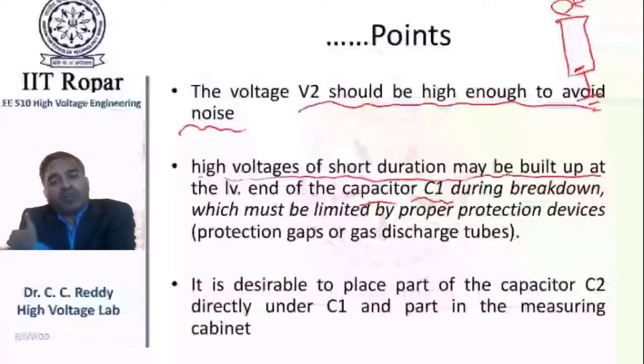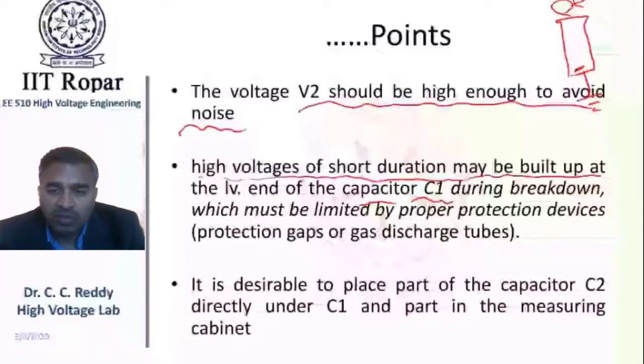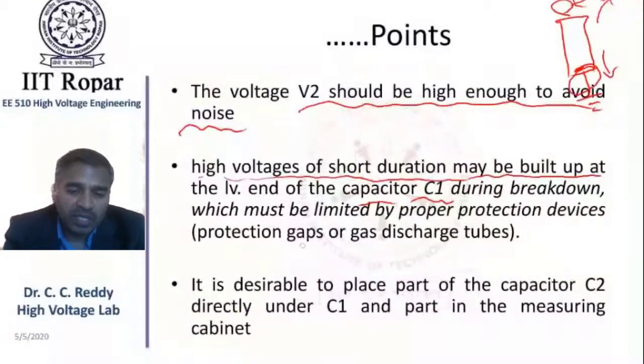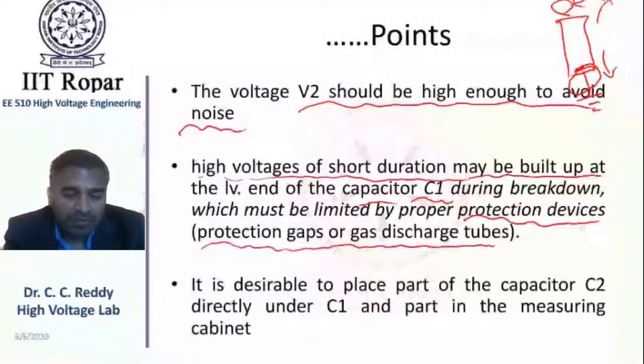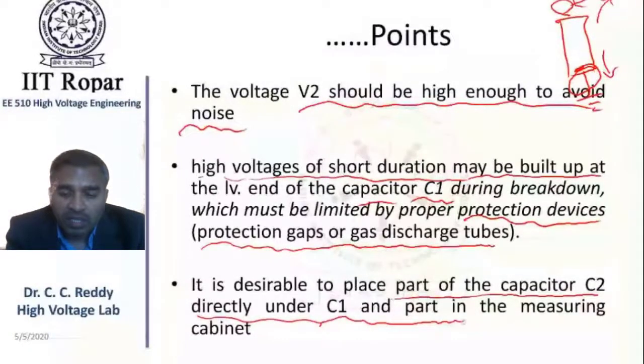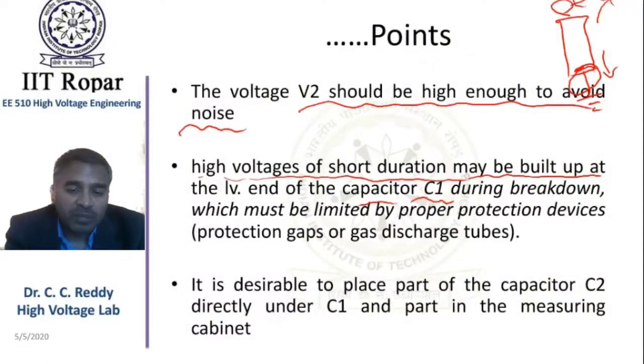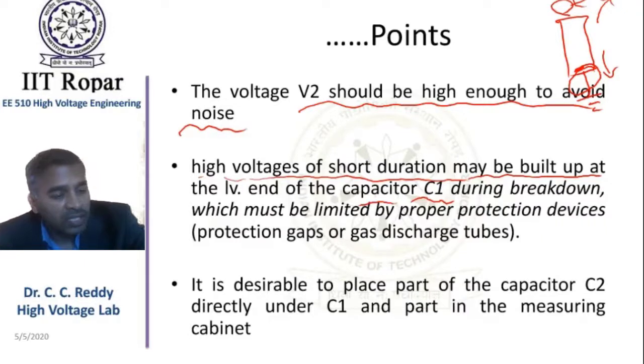So what will happen when breakdown occurs? Sudden discharge of the capacitor takes place, so positive charge and negative charge will go like this. Therefore, a huge peak is possible across capacitor C2. It will induce a huge peak voltage which will travel as a wave to the measuring circuits, and it may damage the circuit also. Therefore, proper protection needs to be taken care of. So protection gaps or gas discharge tubes have to be connected across C2. It is desirable to place part of capacitor C2 directly under C1, as already mentioned, and part in the measuring circuit. So these are some important points about this peak reading, crest reading voltmeter.